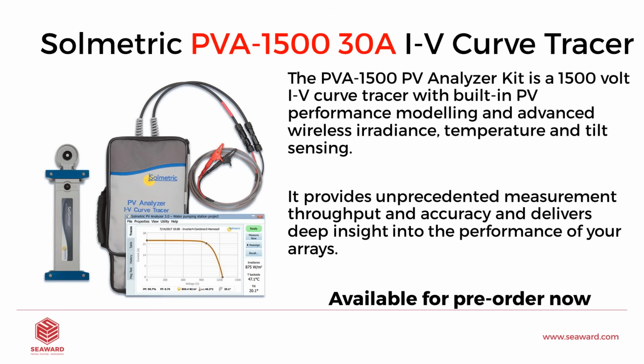The Solmetric is larger, it will give us the full IV curve trace, but it is also a lot more expensive. The other issue is the Solmetric PVA 1500 is not actually available right now. As of this presentation, we expect it to be released at the end of May, and this doesn't really help us with regard to systems we have to test right now. So if you do have a requirement for 1500 volt testing, the way to go would be the Solar Utility Pro. But if you do wish to place a pre-order for the PVA 1500, we are accepting those. Demand is quite high.